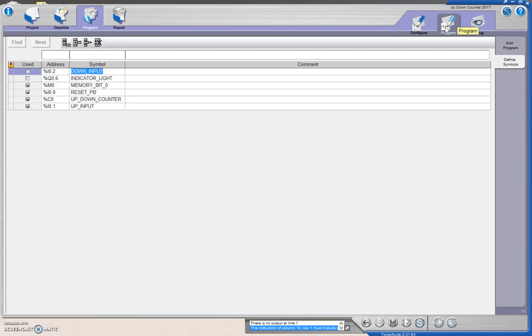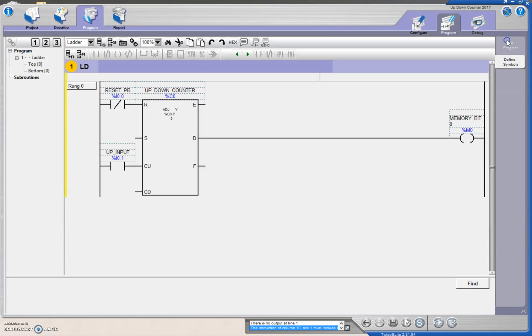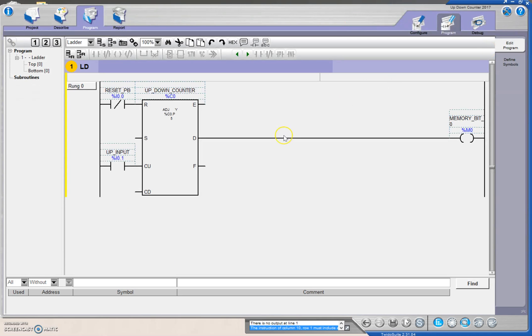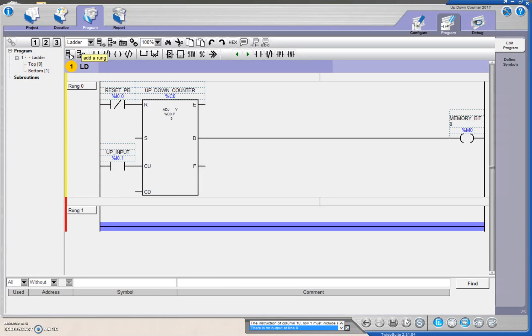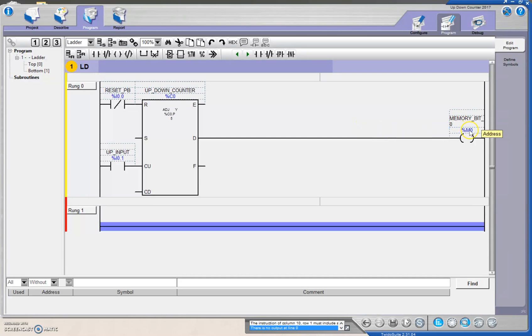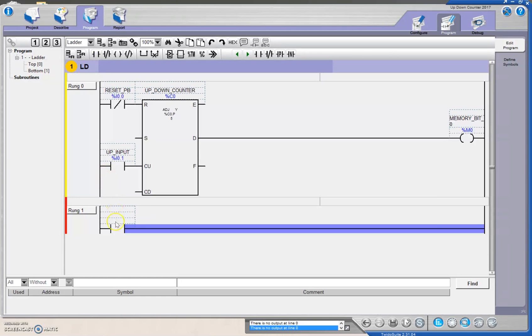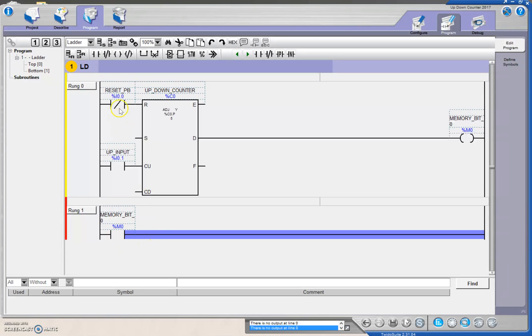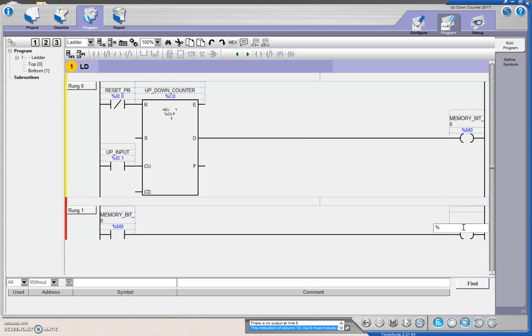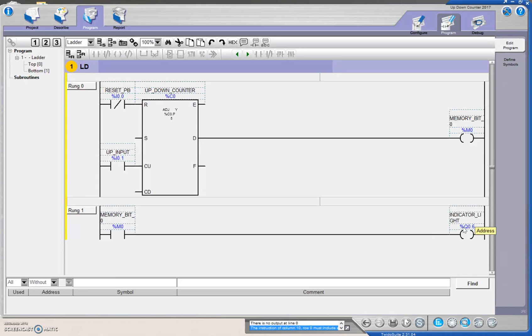We're going to go back to program, we're going to edit the program. We're going to say that, let's drop a rung in, that when that memory bit sets, so when the done bit sets, it's going to turn on the memory bit, that's going to go from a 0 to a 1. We're going to monitor that memory bit. When that memory bit goes to a 1, then we want to turn on that output. And we physically have the output wired to Q 0.6, and there's our indicator light.